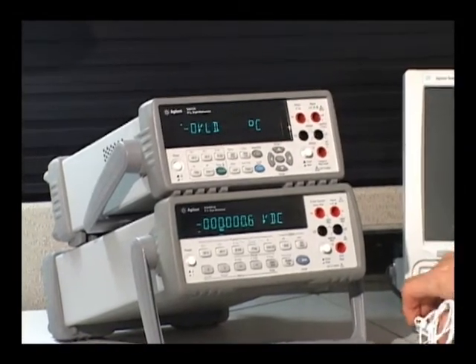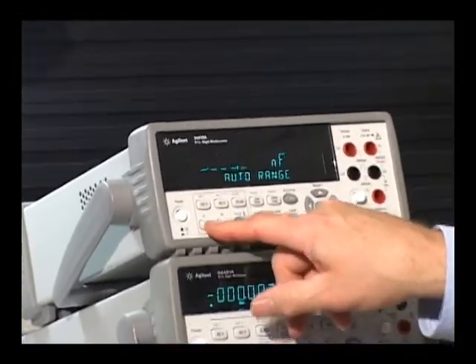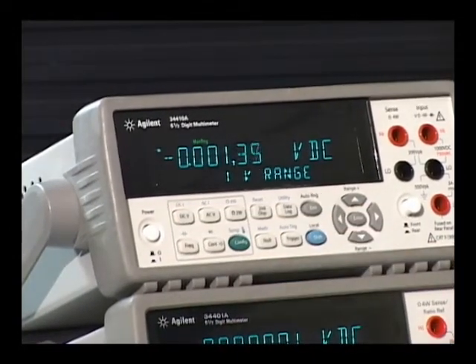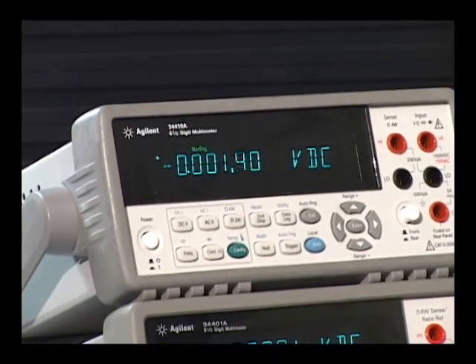Yet another improvement asked for was the ability to measure capacitance and we've added that. Finally, people told us they'd just like to be able to make measurements over lunch or over the weekend. Set me up a data logger. So we've added data logging.